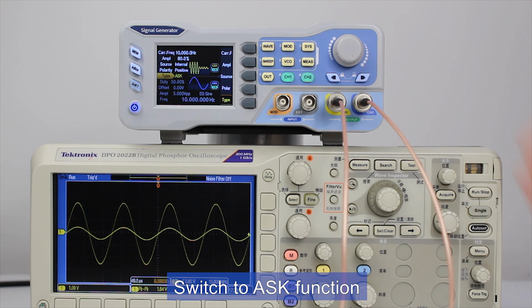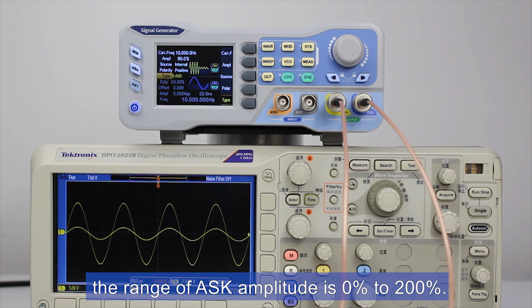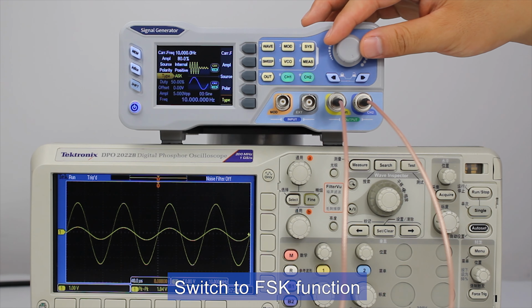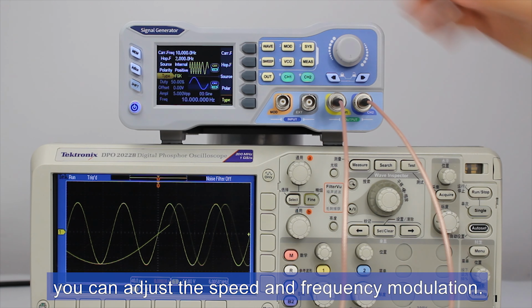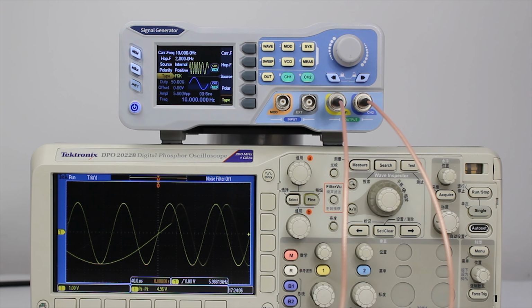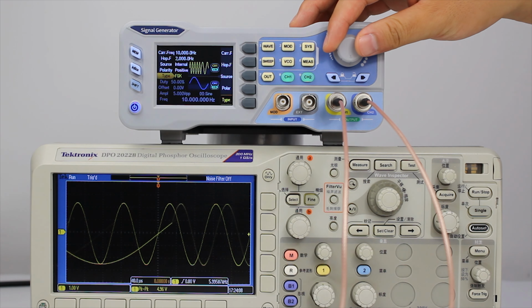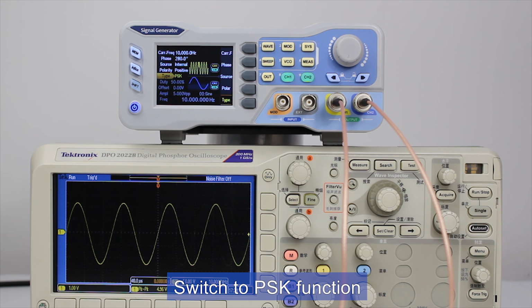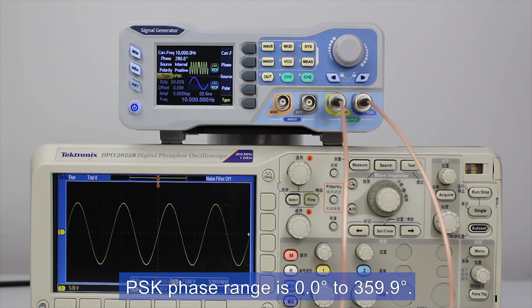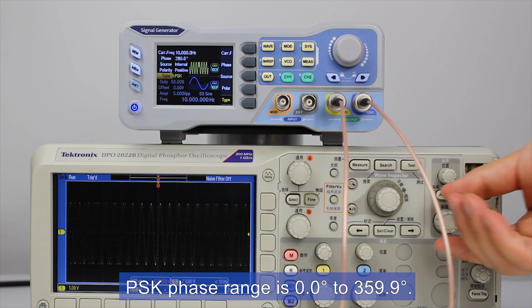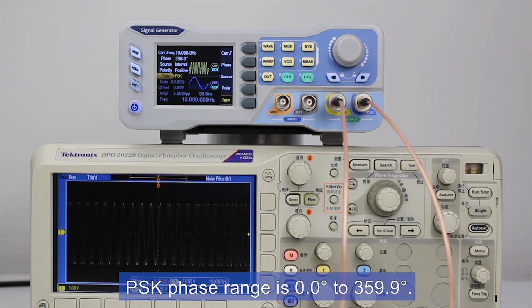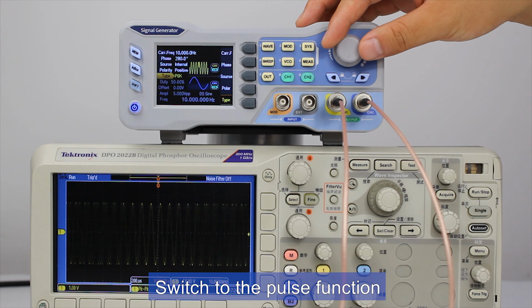Switch to ASK function. The range of ASK amplitude is 0% to 200%. Switch to FSK function. You can adjust the speed and frequency modulation. Switch to PSK function. PSK phase range is 0 degrees to 359.9 degrees. Switch to the pulse function.